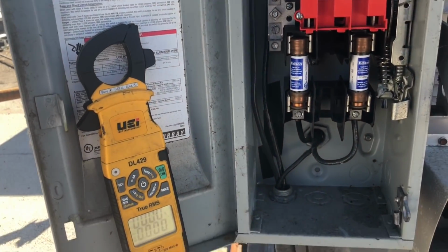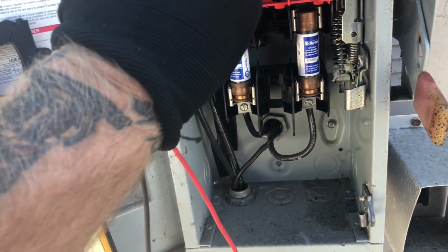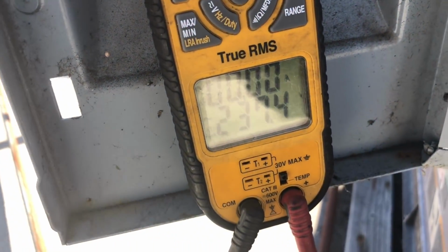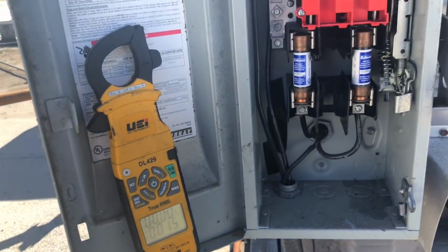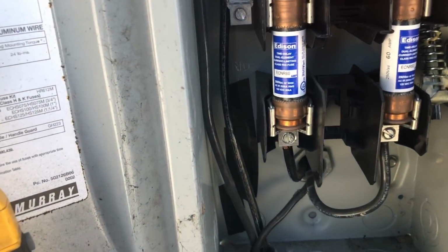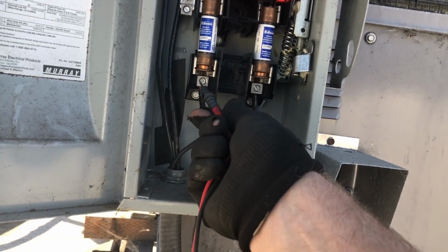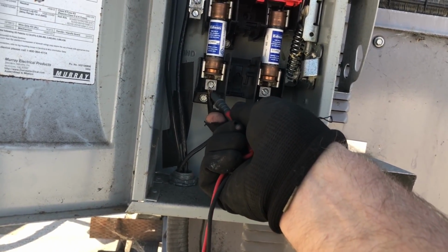We'll start right at the disconnect, go across the top. We got 237. Now I'm going to check the fuses there. Those are 60 amp fuses. The fuses are good, so let's check the bottom of the disconnect here.